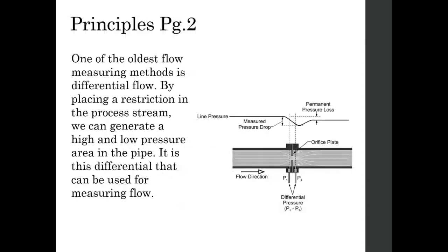One of the oldest flow measuring methods is differential flow. By placing a restriction in the process stream we can generate a high pressure and a low pressure area in the pipe. As we see in the diagram at the orifice plate, the area just in front creates a high pressure area and the area just after creates a low pressure area. This gives us an amount of pressure loss across the front and back of that orifice plate — this is the physics we use to determine the differential pressure.